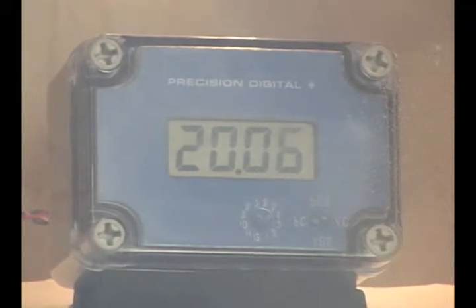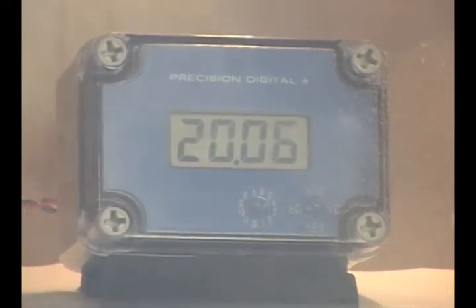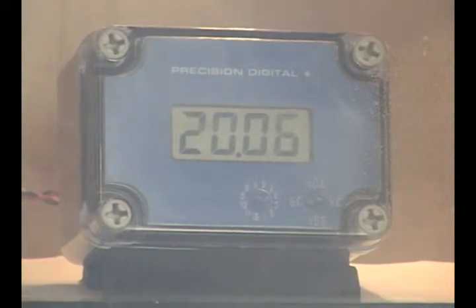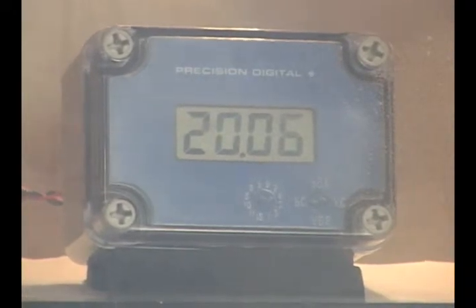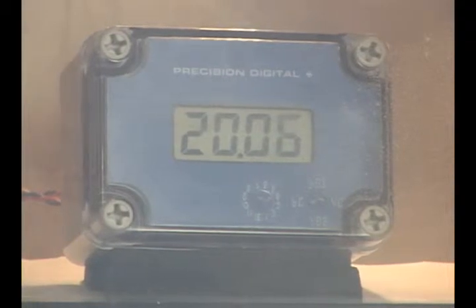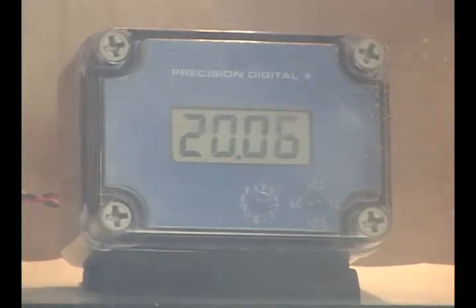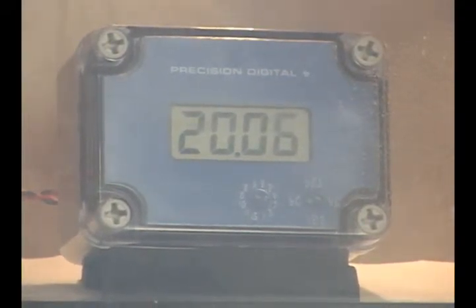To prove that it's actually functional at this minus 55C temperature, I'm going to change the milliamp input and you'll be able to see the display keep up with the changing milliamps, despite the fact that a normal meter would be frozen solid at this point.